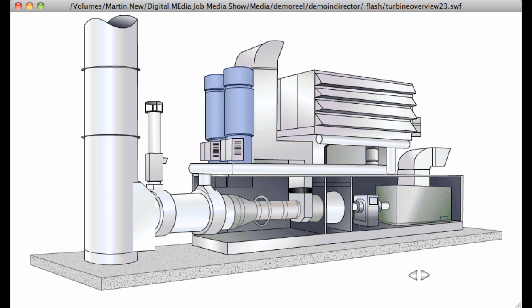Another very visible feature of the unit are these two exhaust fan ducts. The turbine enclosure is held at a negative internal pressure by the electric fans in these enclosures. This design prevents any contamination or gases from being able to escape the turbine enclosure.